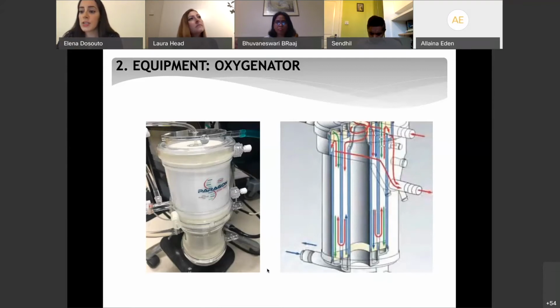So the heat exchanger incorporates fins that channel blood into thin layers to increase heat exchanger efficiency. And then after the blood passes through the heat exchanger phase, it goes into the gas exchanger phase. So blood generally flows outside the fiber, whilst gas flows inside the fiber, and they go in opposite directions, which is what we call countercurrent mechanism. You can see here that the gas goes in this direction and the blood goes this direction. It's the same as if you were running along with your partner and then you sort of touch each other. It's not much of a collision. Whereas if you're running towards each other, it's going to be more of a clash. So it's going to be like an enhanced touch, an enhanced gas exchange.